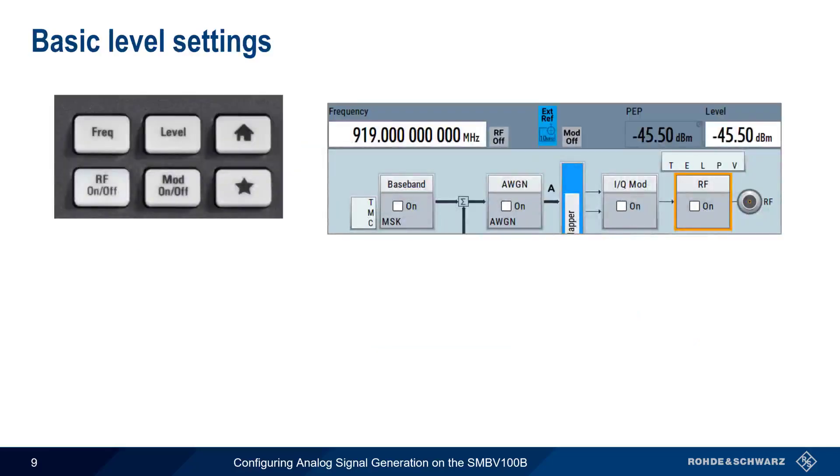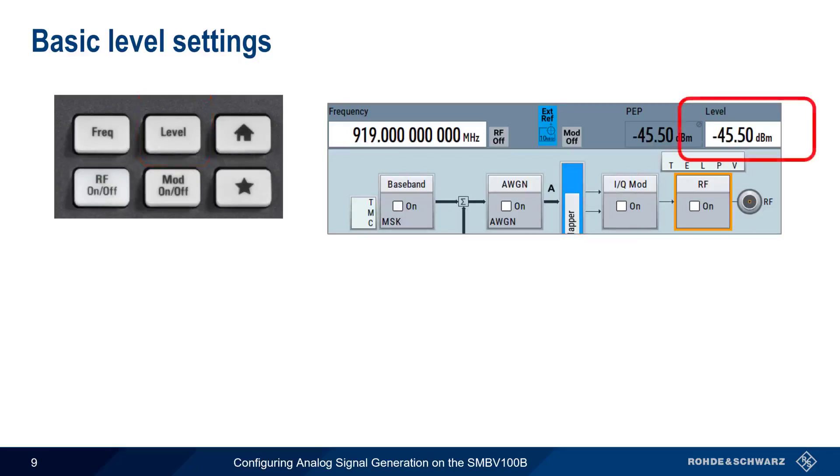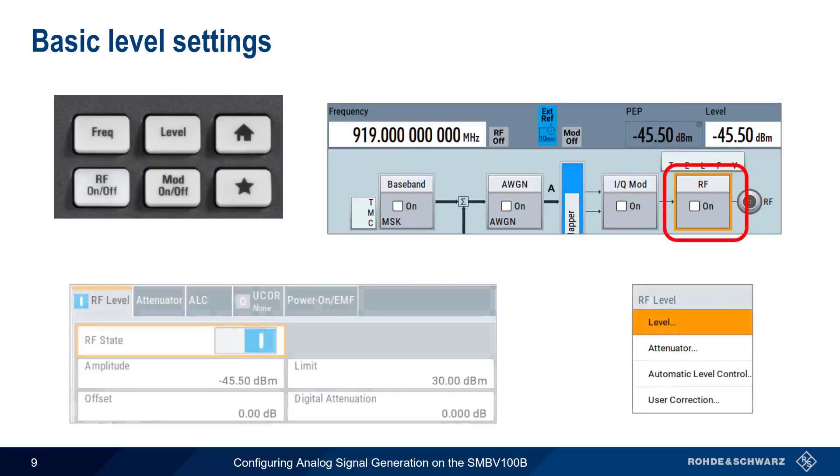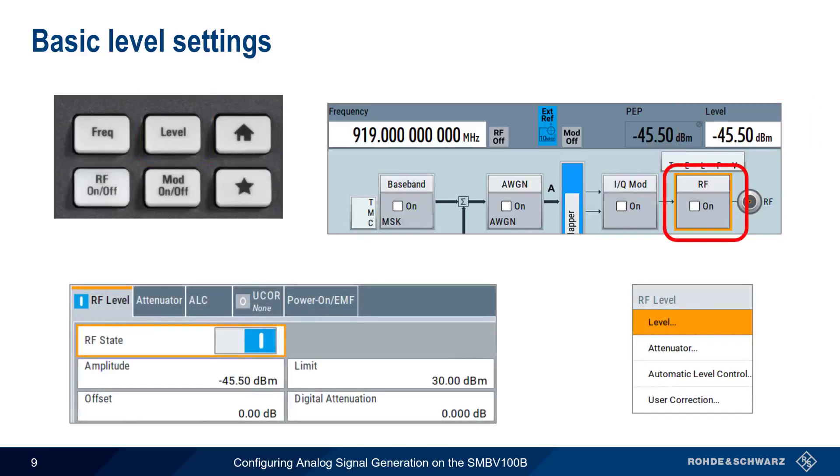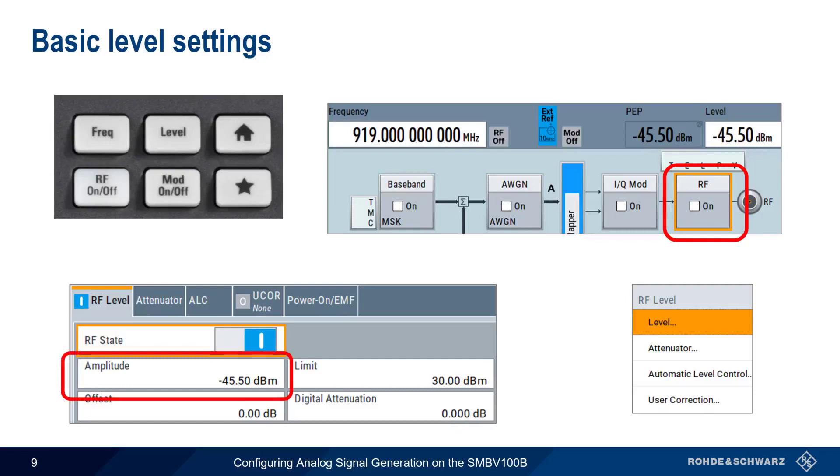Now that we understand the frequency and phase settings, let's move on to Level. As with Frequency, we can set the level of our generator output using the Level Hard key, clicking on Level in the Status bar, or by clicking on the RF block and choosing Level from the menu. The Level coming out of the SMBV is always the same as the Level, or Amplitude, entered in the RF Level menu.